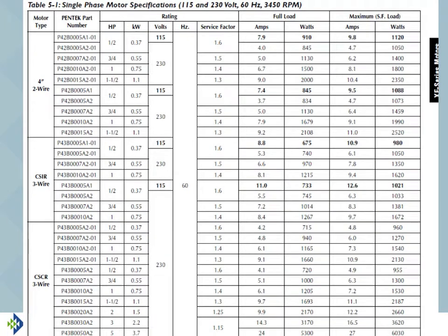Now, this is out of the PN 793, and when we look here, there's your CSIR, here's your CSCR. So what we're going to do next here is look at max load or service factor amps. You'll notice they're over there on the right-hand side of the page. And there's your amps, and we're going to look at a P43B0010A2 because 1 horse is the largest that you can go with the CSIR control box. And so you'll notice there the max load amps are 9.7. Take the exact same motor, P43B0010A2, in your CSCR, and now your max load amps are only 7.2.